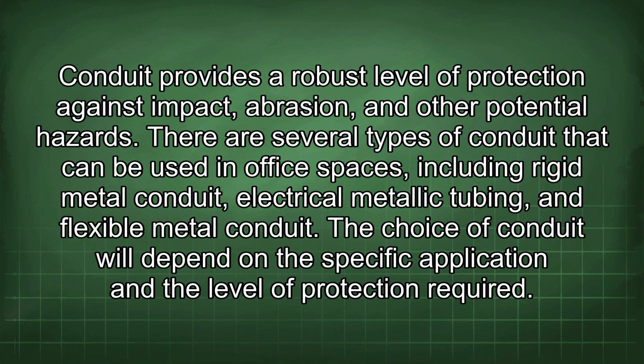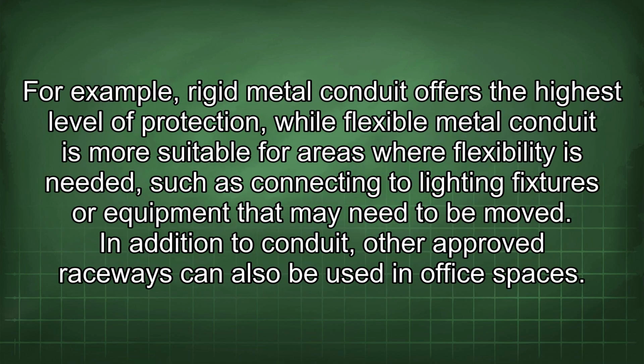There are several types of conduit that can be used in office spaces, including rigid metal conduit, electrical metallic tubing, and flexible metal conduit. The choice of conduit will depend on the specific application and the level of protection required. For example, rigid metal conduit offers the highest level of protection, while flexible metal conduit is more suitable for areas where flexibility is needed, such as connecting to lighting fixtures or equipment that may need to be moved.